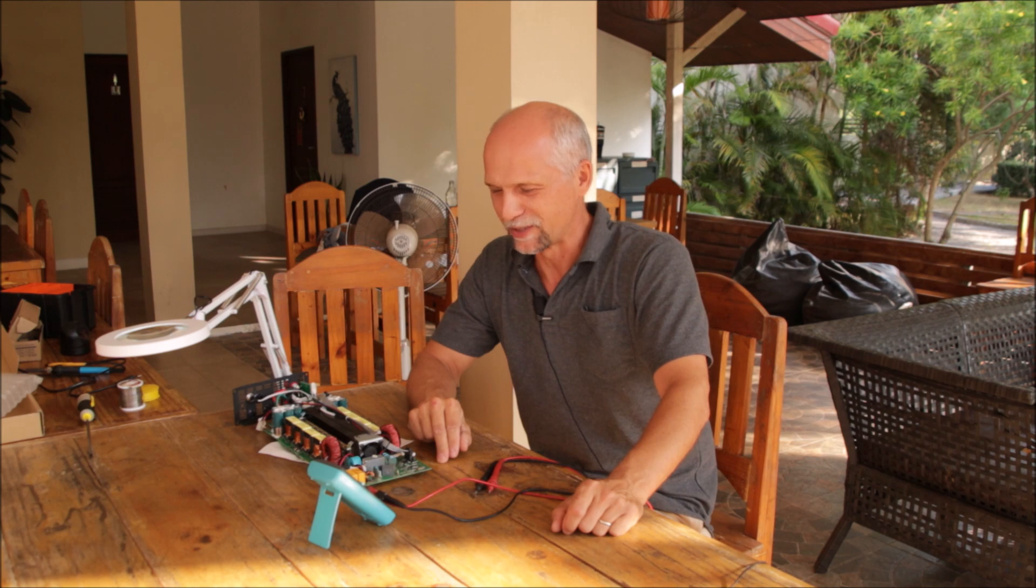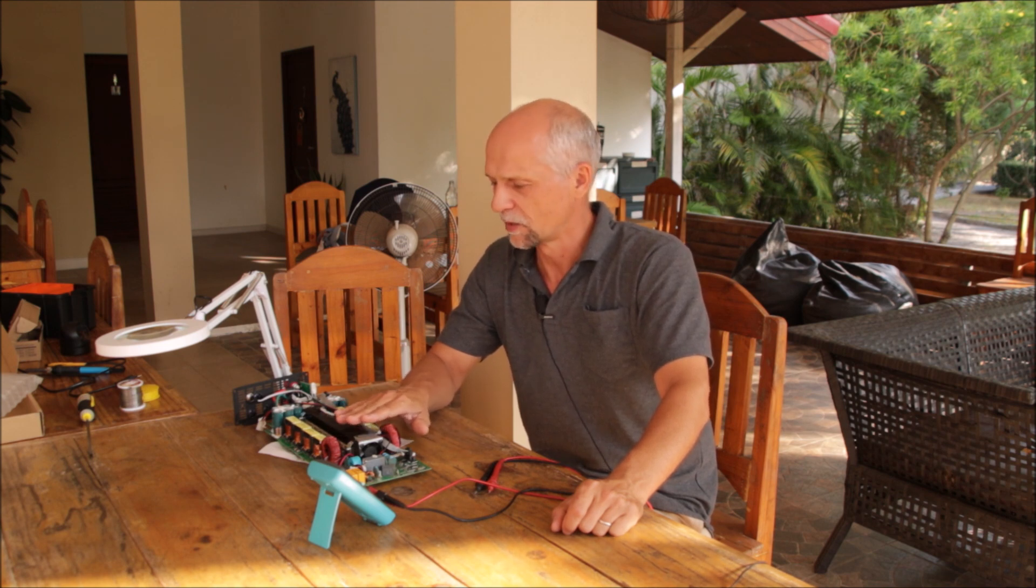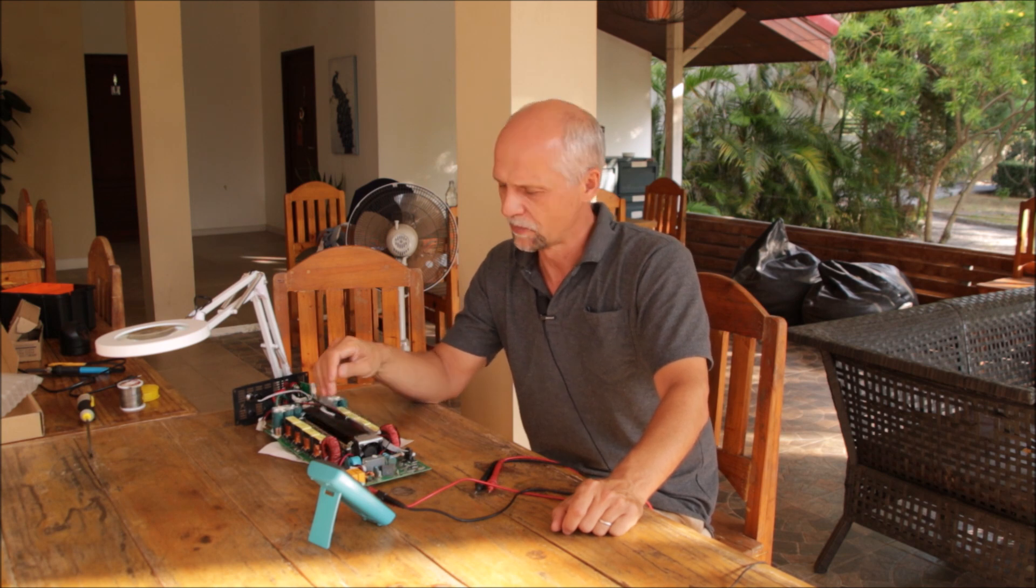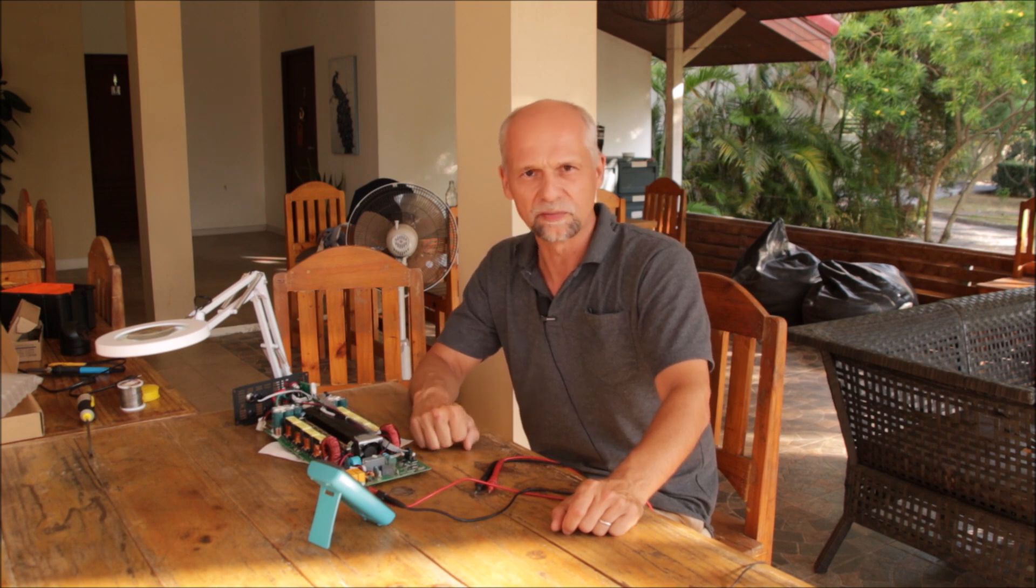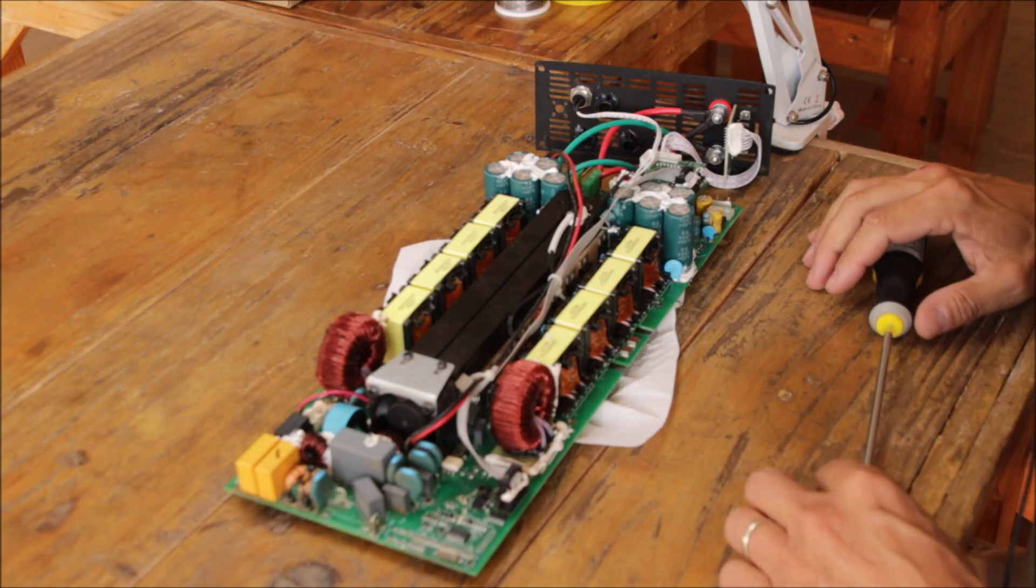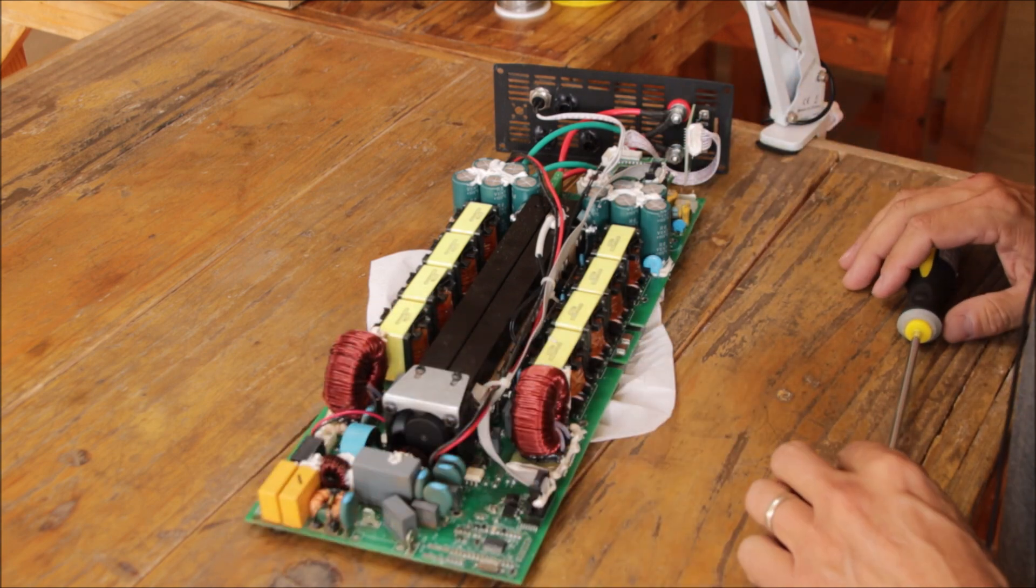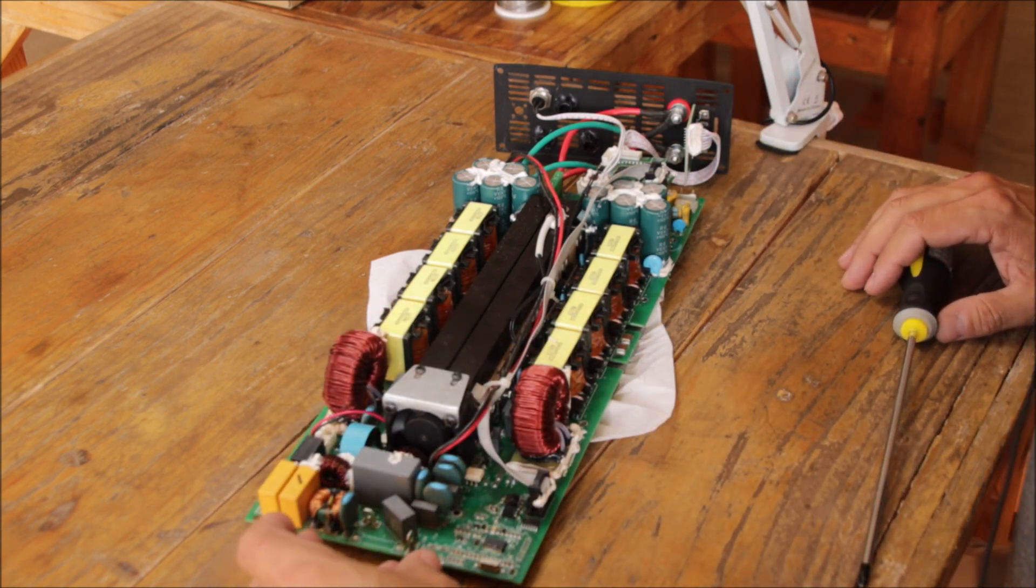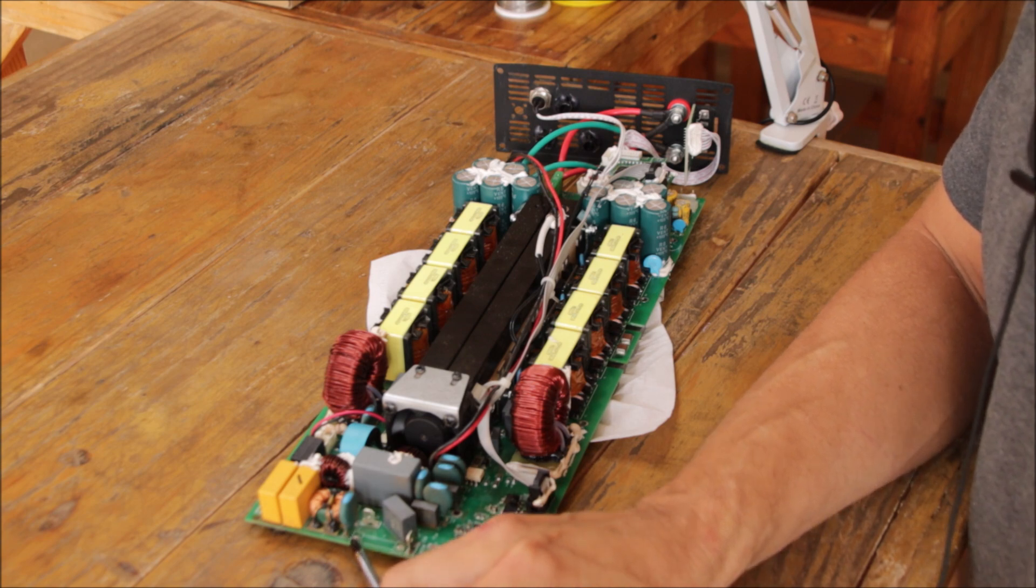Let's take a closer look at this inverter. I'll tell you the standard issues which happen when you have an AC fault on the Sun inverters. This is the power board of a Sun 2000 inverter. This side is DC, this side here AC. The AC input comes from here, and the first thing which can fail is the fuse.